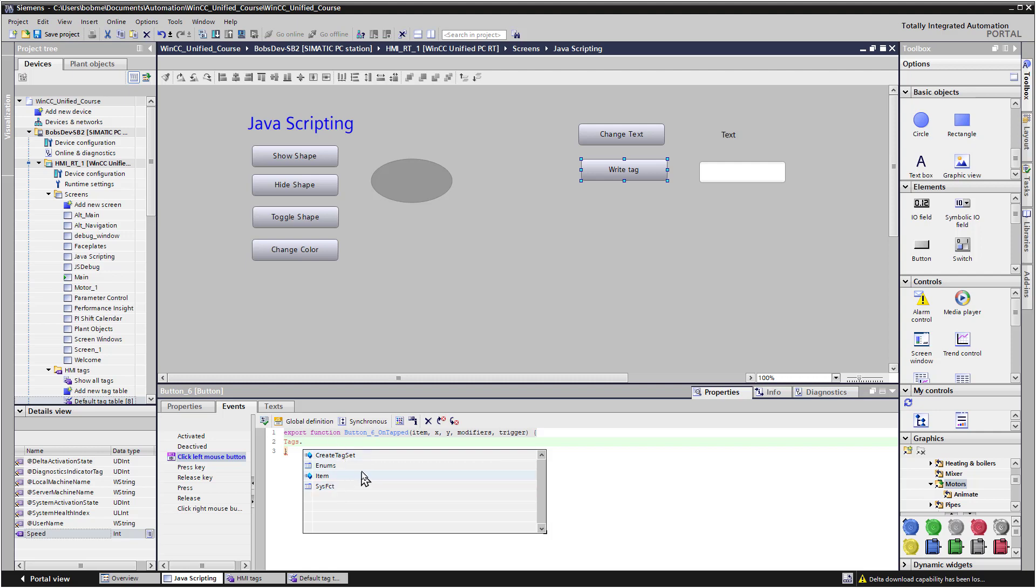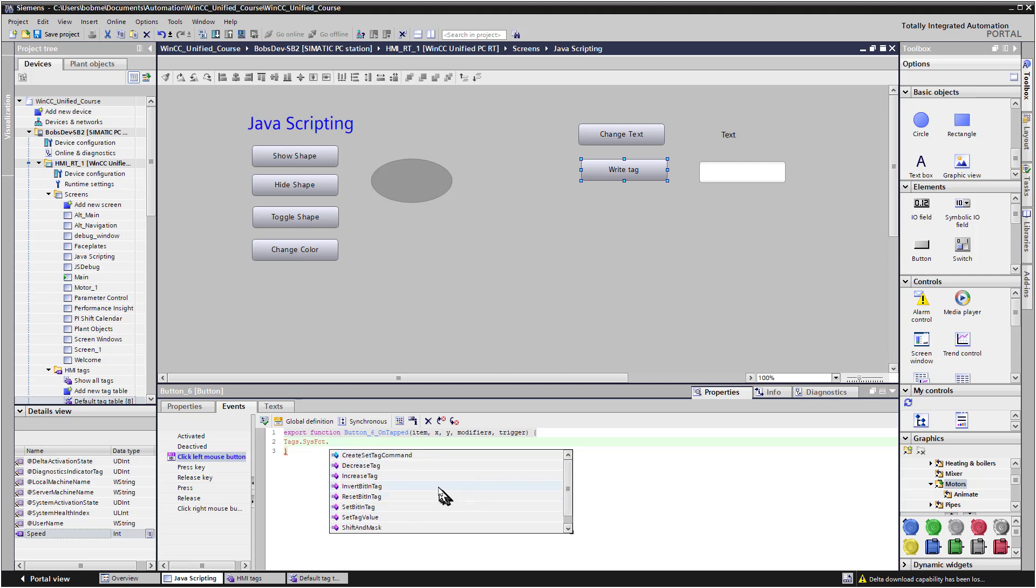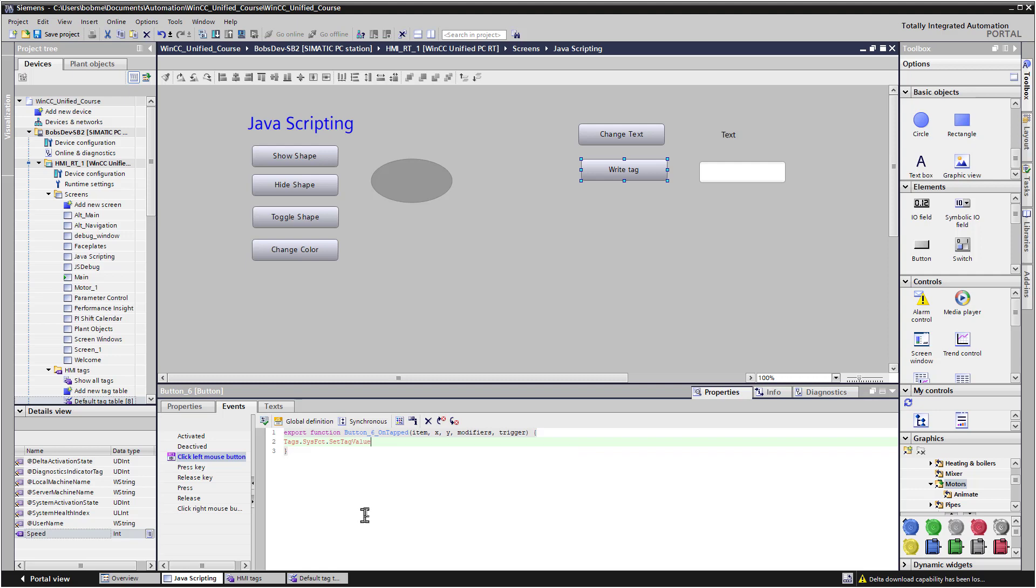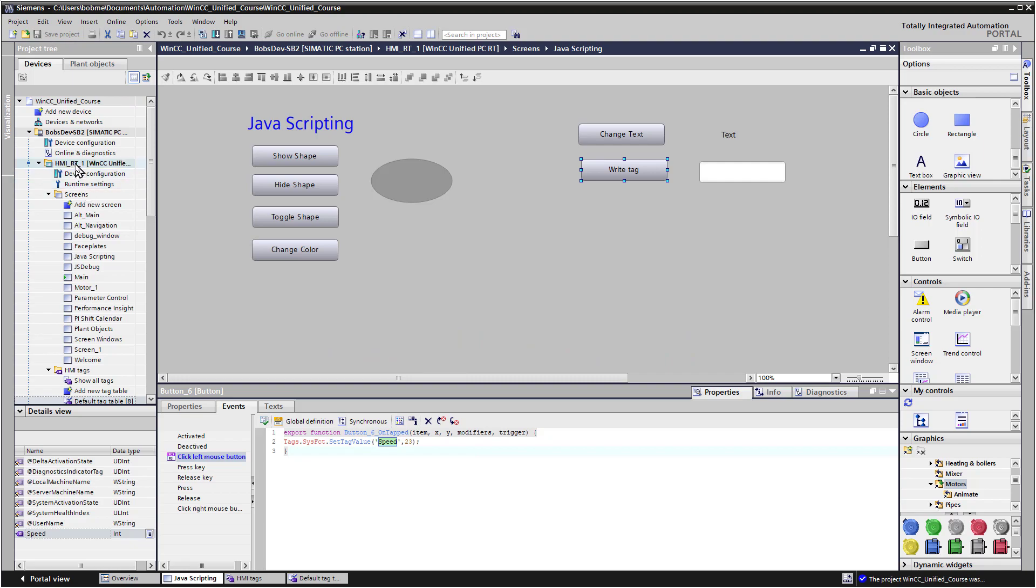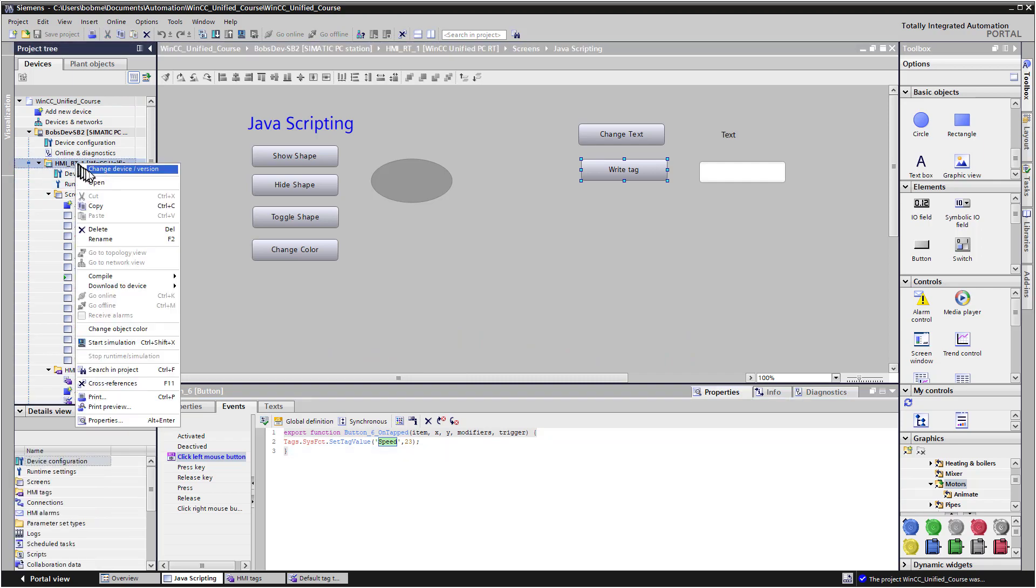So one way to write to a tag is just use the sysfunct and place a dot. And it gives us some functions. So we can set tag value. We can set a bit in a tag, reset, invert a bit, all kind of options. So we could use set tag value. And if we put a parentheses, you can see it's asking for the name of the tag that you want to write to and the value you would like to write to it. So the name of our tag is speed. So you have to make sure you get the case right. And we'll just write a 23 to it and add a semicolon. So we'll save this and just test this out in runtime.